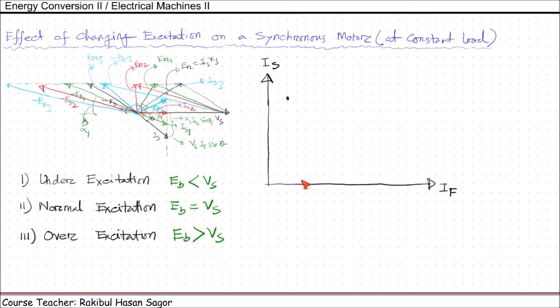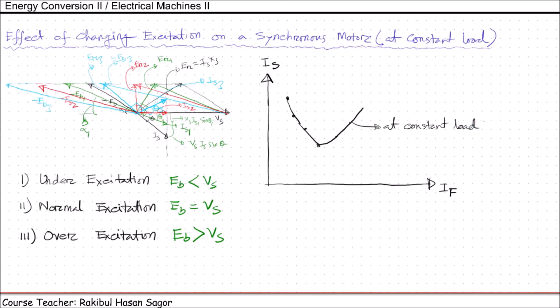For this particular field current, we are getting this Is current. Now if we increase field current, that means we are increasing excitation. In that case, initially the armature current will start decreasing. So for a higher amount of field current, the armature current will be decreasing. If we keep plotting, the armature current will be minimum at this point. Then if we keep increasing the field current, that is if we keep increasing the excitation, again the armature current will start increasing. So if we connect all the dots, we will get a shape like this. This is at constant load — suppose that load is L1. You will find this curve will look like a shape of V, English letter V. That is why it is called the synchronous motor V curve.